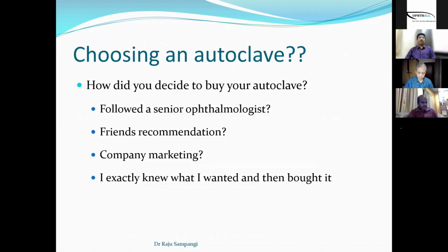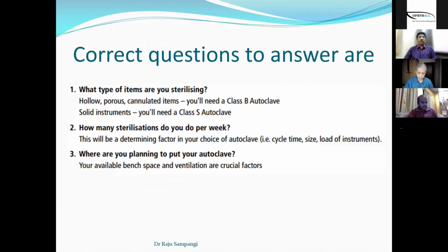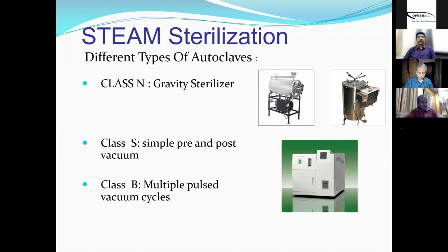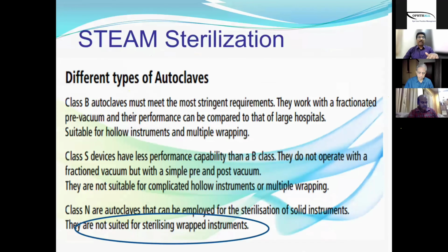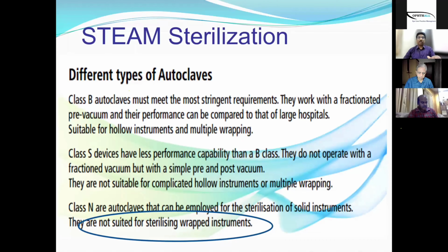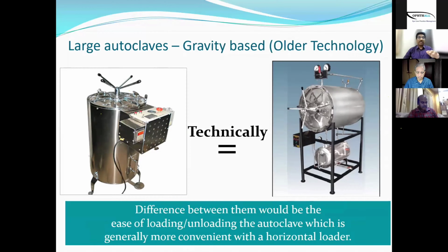Then choosing the autoclave, as I was just discussing. The correct questions to answer when you're choosing your autoclave are: what type of items are you sterilizing? Are you sterilizing hollow, porous, or cannulated items? If your answer is yes, then you'll need a Class B autoclave. So if you see here, steam sterilization can be of Class N, Class S, or Class B type. And the Class N type is not suitable for sterilization of wrapped instruments. And if you see autoclaves, the large autoclaves, you can have a vertical autoclave or a horizontal autoclave.